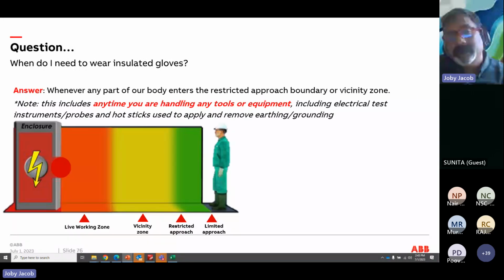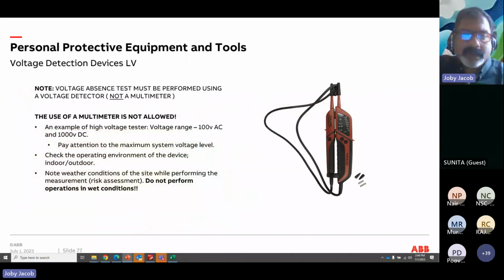Why we use insulated gloves, where we insulate, particularly when we are entering the prohibited approach boundary, when you are entering into live working. So when inserting your hand into your switchgear, it's always a habit not to insert bare hands into any cabinets, even though it's isolated. There could be some source of supply from somewhere, or a leakage, or a backfeed, or from a UPS, or, if it's a permanent magnet moving coil motor, if it's turned from the other side, it can act as a generator. All those things should be considered as a part of your risk assessment when you are inserting your hand into the panel.